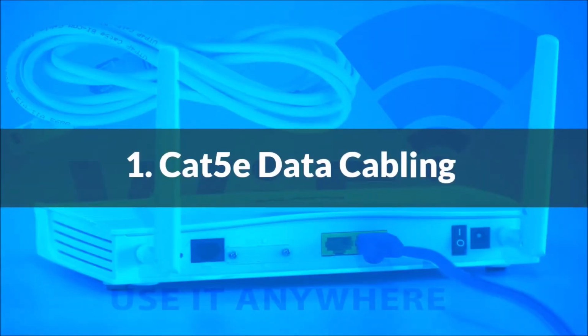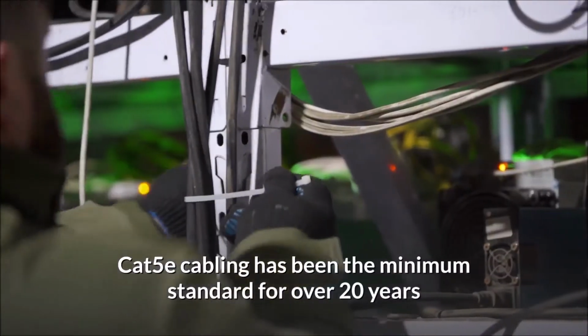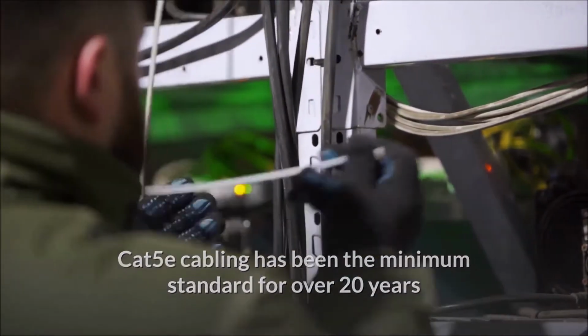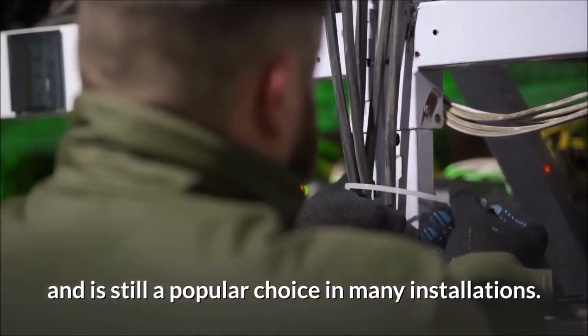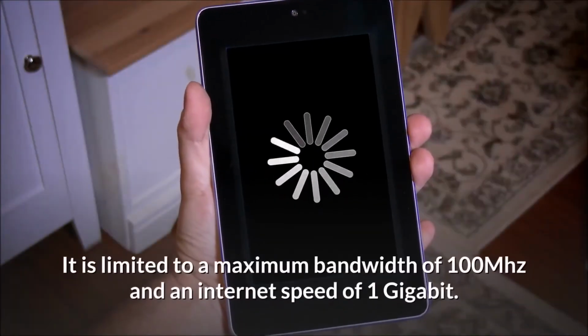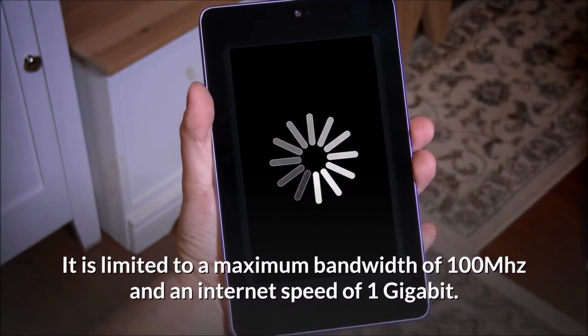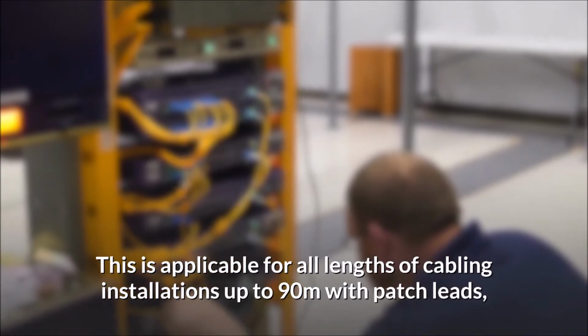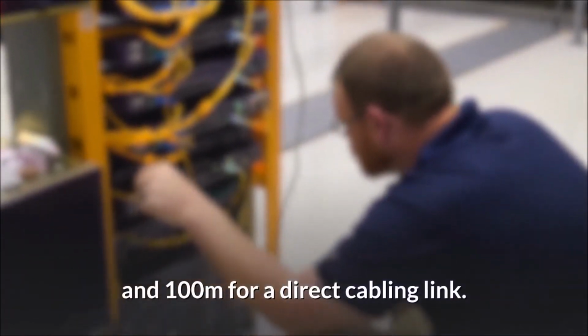1. Cat5e data cabling. Cat5e cabling has been the minimum standard for over 20 years and is still a popular choice in many installations. It is limited to a maximum bandwidth of 100 MHz and an internet speed of 1 gigabit. This is applicable for all lengths of cabling installations up to 90 meters with patch leads, and 100 meters for a direct cabling link.